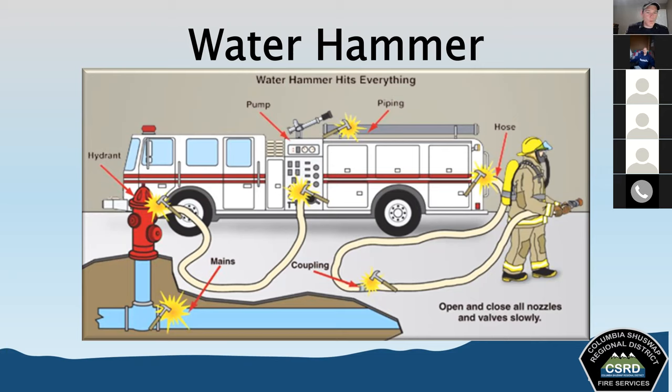The water hammer can cause the hose to rupture. It can cause couplings to separate. It can cause damage to the plumbing on a fire apparatus, even damage to the underground piping system, depending on how bad it is. A similar situation can occur if the valves open too quickly and a surge of pressurized water suddenly fills those. Again, water does not compress. We need to be very slow and methodical with the way we move our water.